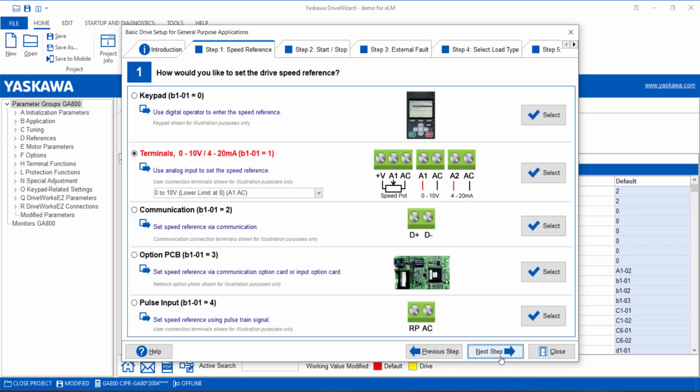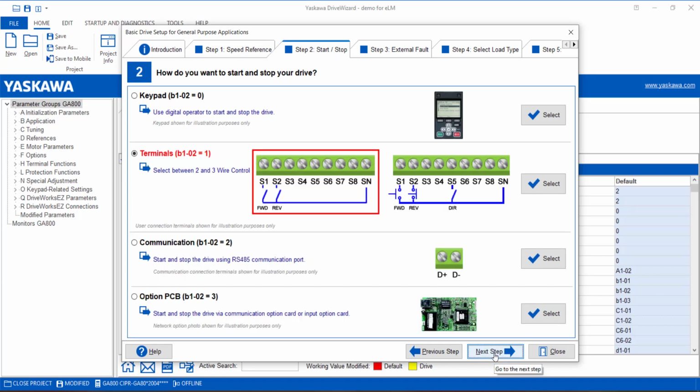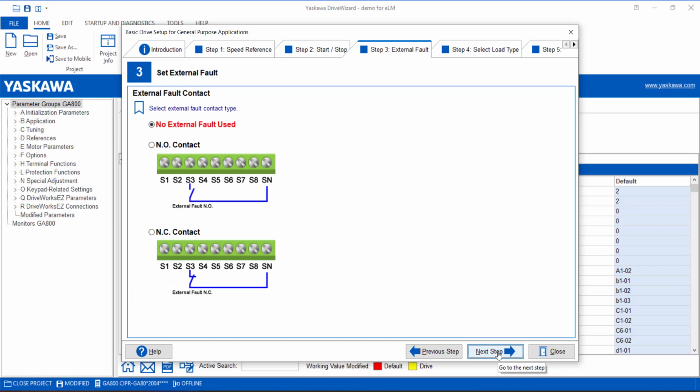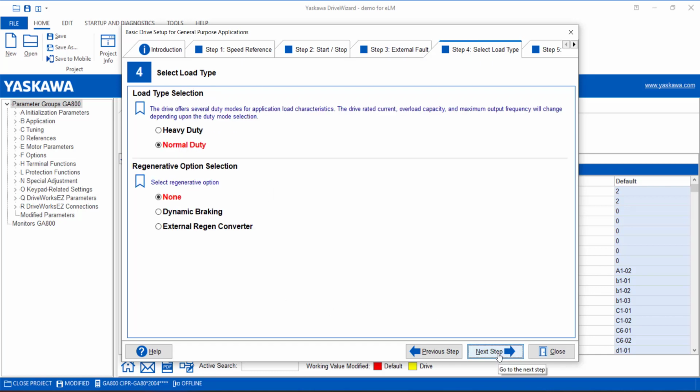Now simply just follow the steps. Select the reference source. Is it coming from the keypad, terminals, a network, or a pulsed input? Then the run source. Is it coming from the keypad, terminals, or network? Are you using an external fault input? If so, it can be set up for normally open or a normally closed contact. Select the load. Are you using dynamic braking?